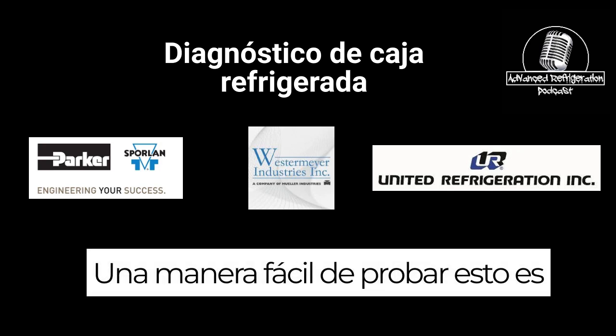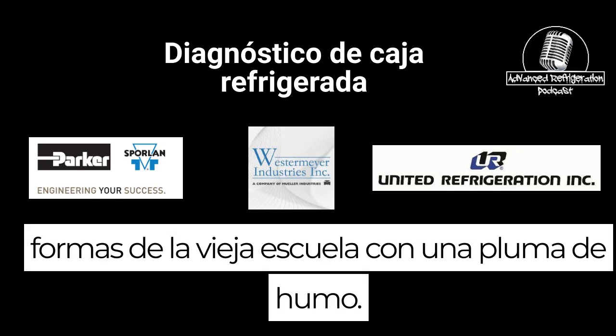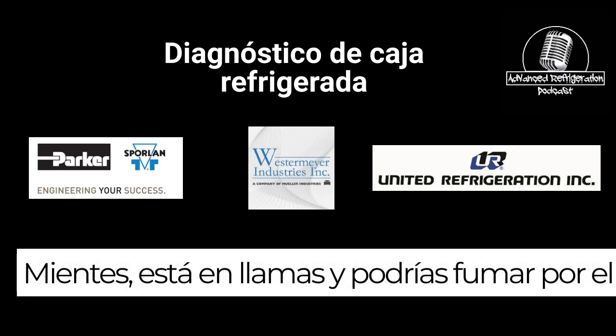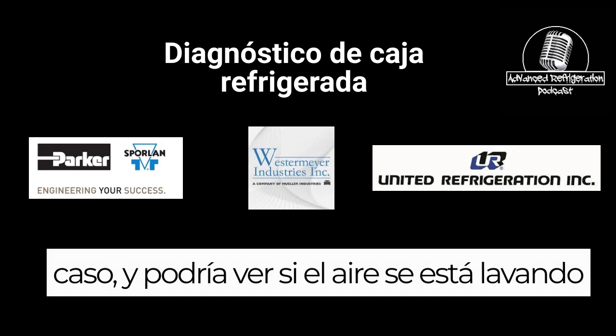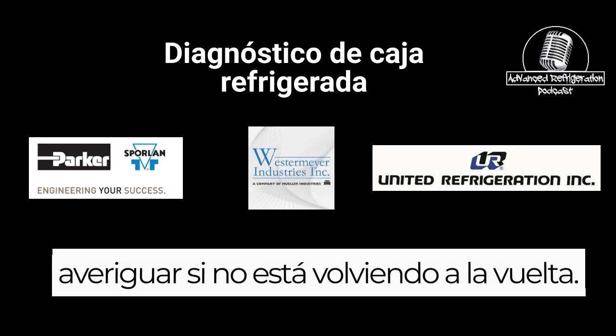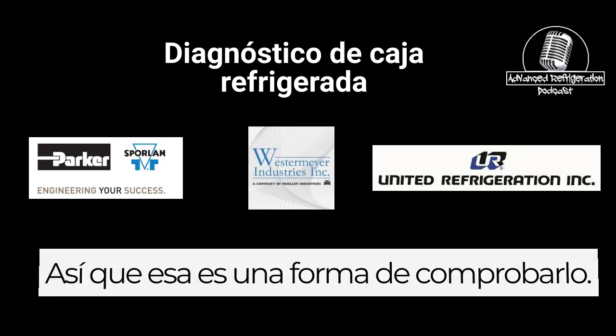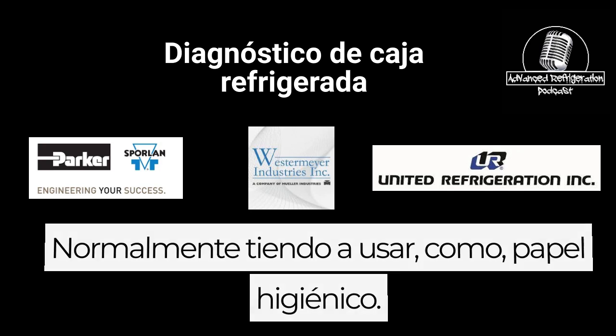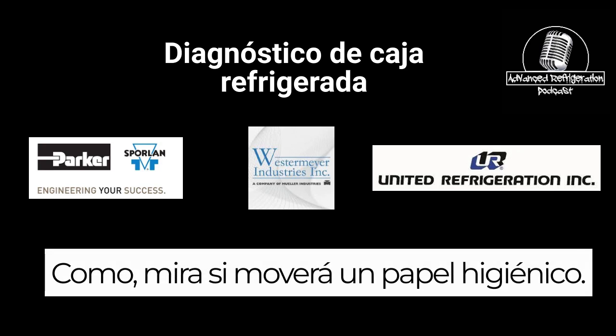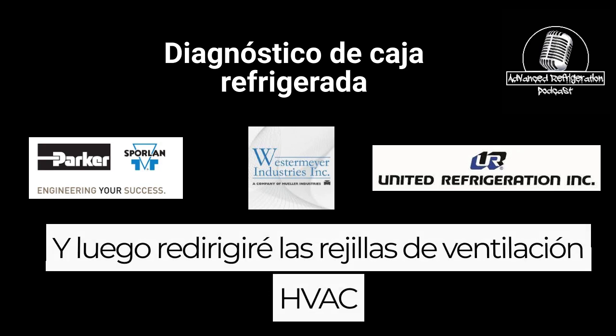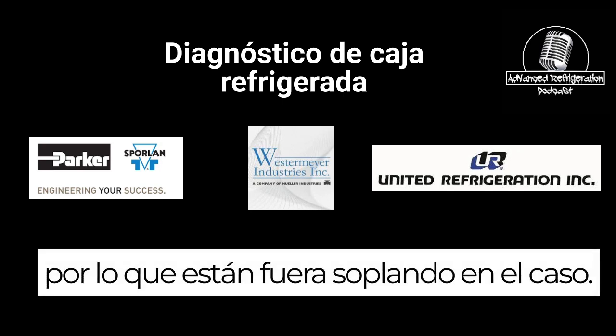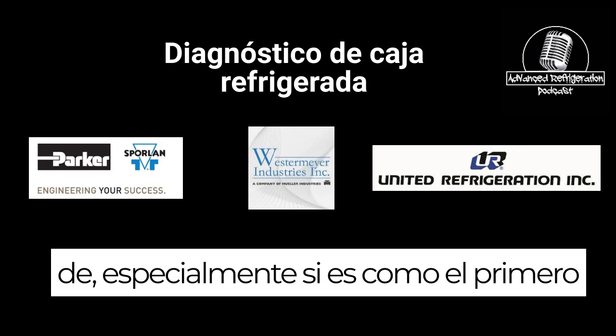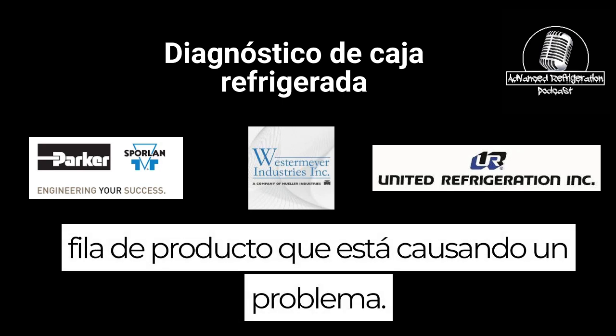One easy way to test this is the old school way, with a smoke pen. You light it and you can smoke out the case and see if the air is getting washed out, if it's not making it back to the return. So that's one way to check it. I typically tend to use toilet paper if I think something's blowing in there, to see if it'll move the toilet paper. And then I'll just redirect the HVAC vents so they're not blowing in the case. So that's one thing to be mindful of, especially if it's the first row product that's causing an issue.